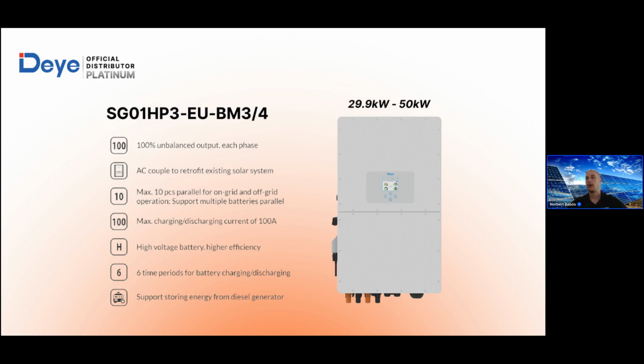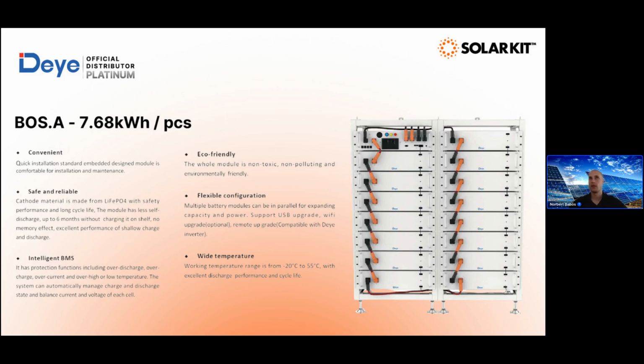And for this kind of inverter and for this new generation, we have the BOS-A batteries, which are roughly 7.7 kilowatt hour per piece. In total, you have here 15 pieces. It's an indoor installation, so you have to install it within the house or wherever you install it, the factory. It's easy to install, easy to extend later if you would like to. You can reach a maximum of 100 kilowatt hour capacity altogether, combined with a 50 kilowatt or later an 80 kilowatt hybrid inverter.